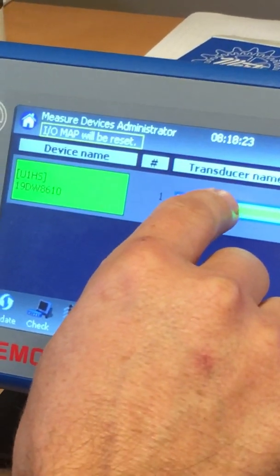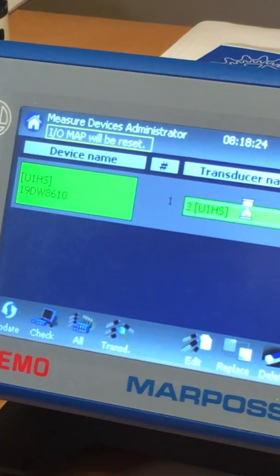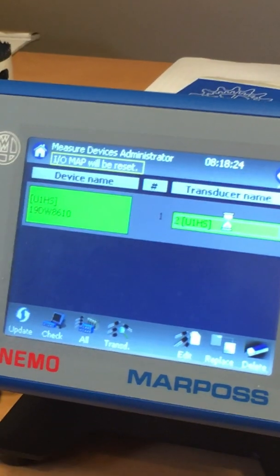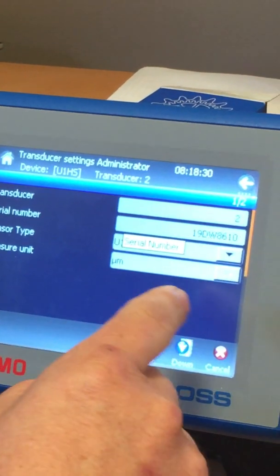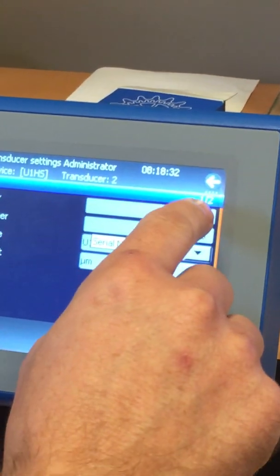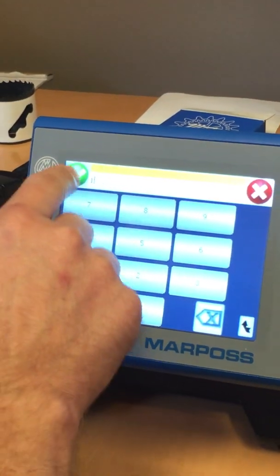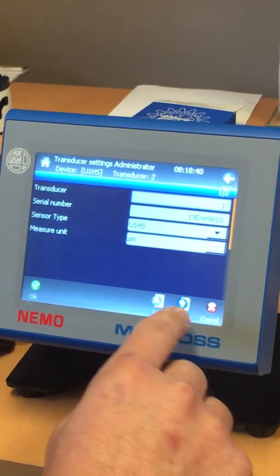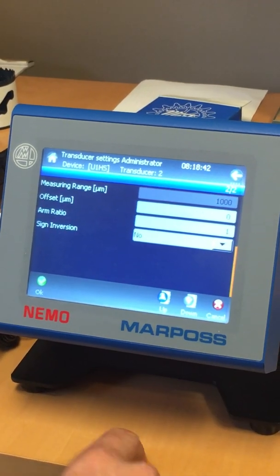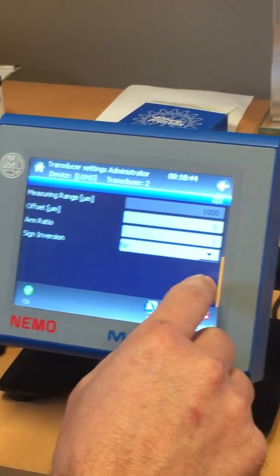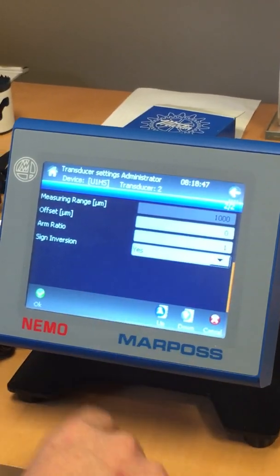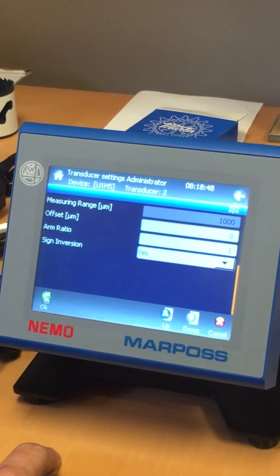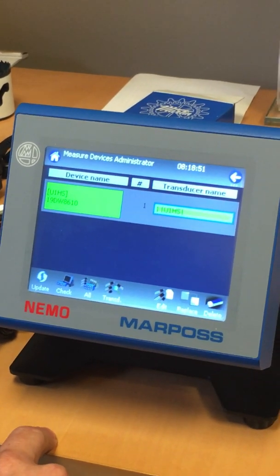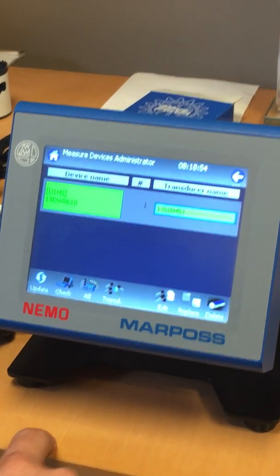From here, we need to go into the transducer name and change some parameters. Double-click the transducer name. The transducer will need to be changed from 2 to 1. Go down to the second page and you'll need to change the Sign Inversion from no to yes. Hit OK. Once this is done, the LVDT is ready to use.